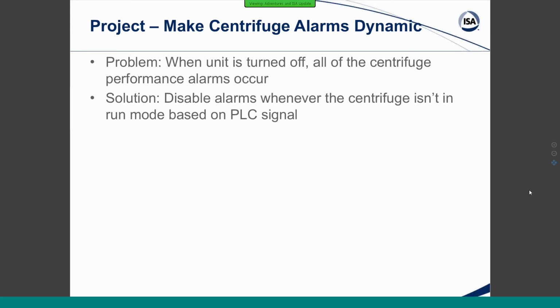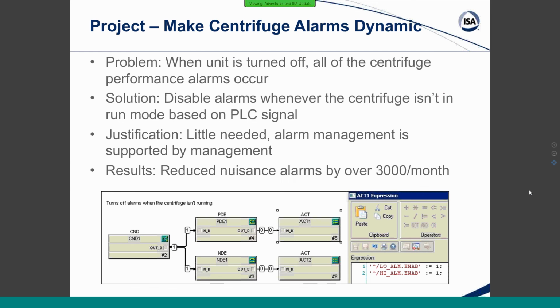So, the solution on this one: we brought in a status mode from the PLC controller, brought that into the DCS, and then set up a little logic base there in all of our alarms that disables the alarm when the centrifuge is not turned on. Here we've got a condition block that's going to a positive and negative edge trigger. If we go to the positive edge trigger, then that will enable all of those alarms, and the reverse if that signal goes from 1 to 0.